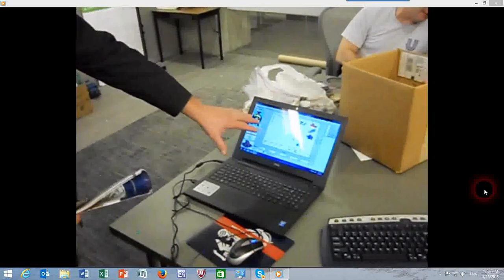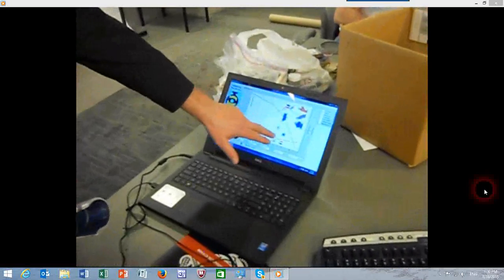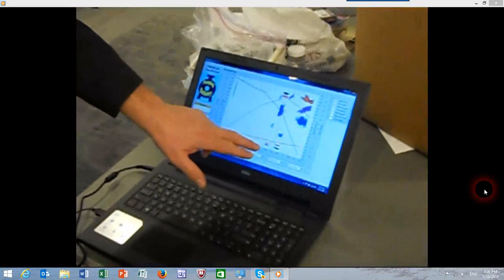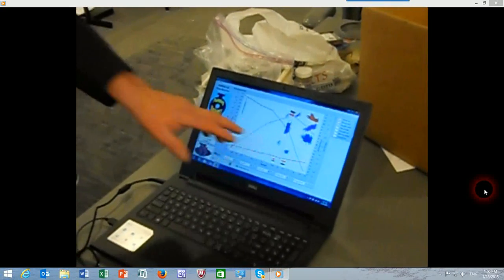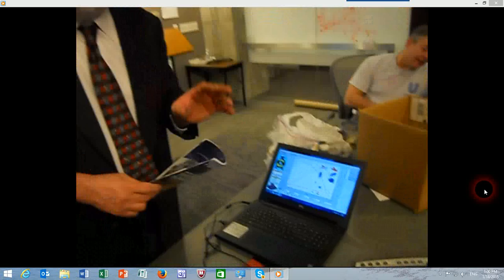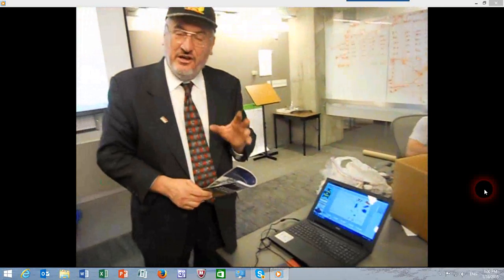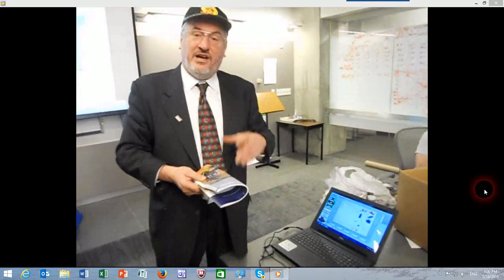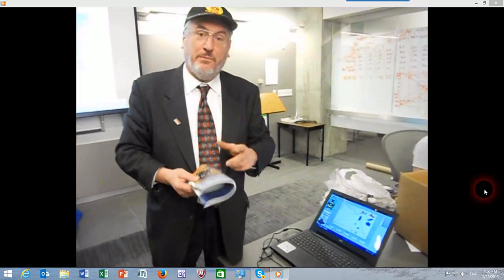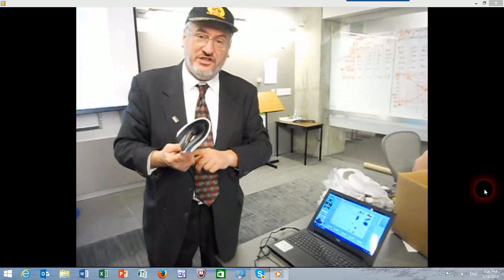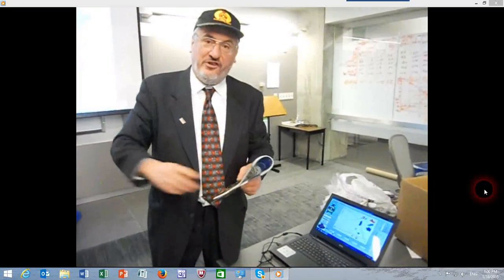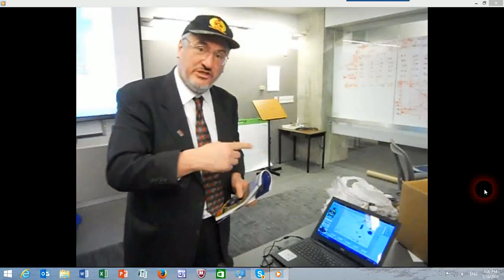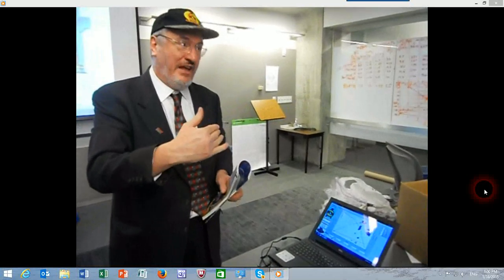So we can see that here, performance live, and then the difference between the horsepower as is versus the horsepower that it should be is shown as an energy loss per year in dollars. The input for that is the kilowatt-hour cost and the percentage of the year the pump runs on average, and based on this calculation and the data, it produces this curve compared to the standard curve.